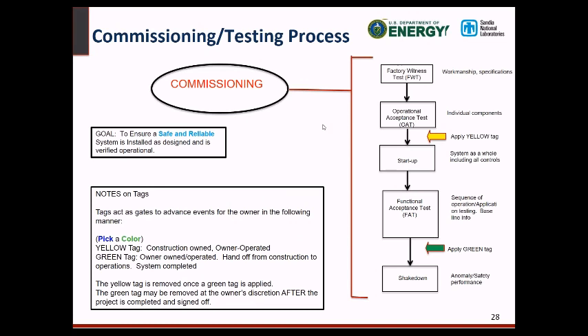Here's just kind of an overview of the commissioning process. The goal is basically to ensure a safe and reliable system is installed and designed and is verified operational. What we have here on the right side is showing the factory witness test, or factory acceptance test, going out there making sure everything is great, that it has great workmanship. Then once the systems have been proven they can turn on and off, it's brought out to your site and you do another test. It's almost like a factory acceptance test, but now it's called an operational acceptance test. This is at the site looking at the different systems and the subsystems, making sure they work and they're reliable.